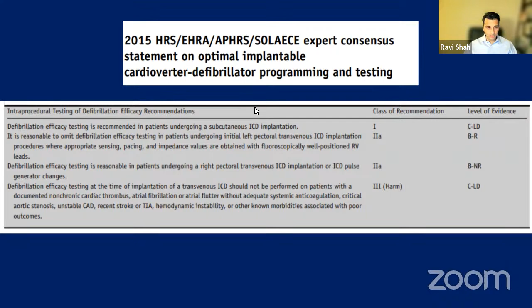How do we define a high defibrillation threshold? If you need more than 25 joules as an absolute value to abort or to defibrillate, it's a high DFT, or if the safety margin is less than 10 joules below the maximum device output. Reportedly, this occurs in between 2 and 24% of patients, but it's hard to pin down a number.